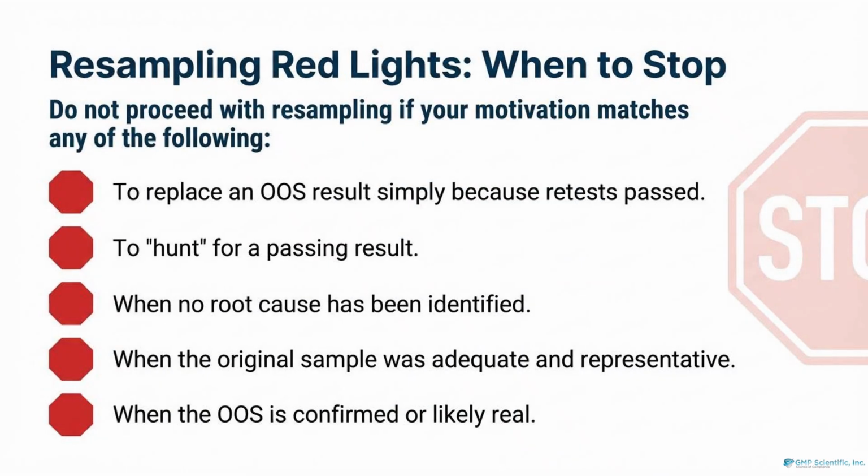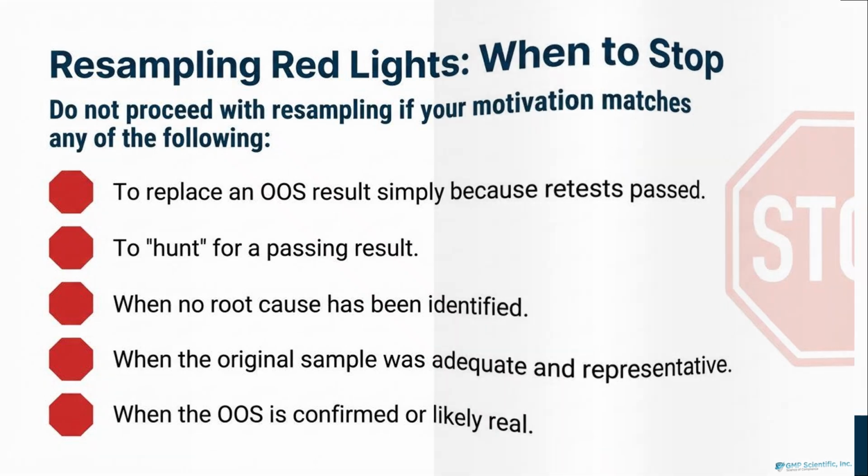Know when to stop. Do not proceed with resampling to replace an OOS just because a retest passed, to hunt for a passing result, or if no root cause has been identified. If the original sample was adequate, the OOS must stand.